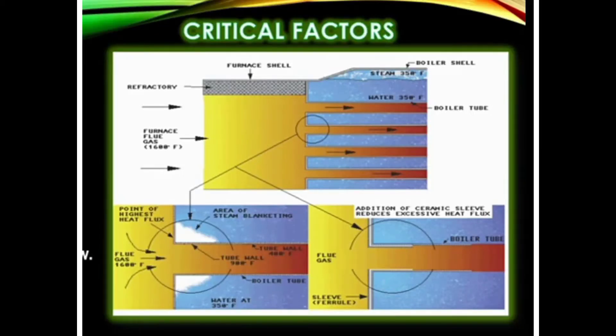Welcome back to learning. Today we are going to discuss steam blanketing, which is one of the causes of boiler tube failure. You can see in this slide that flue gases are coming from the left side at 1600 Fahrenheit and entering into the boiler tubes. This is a water tube boiler, where water is inside the tubes and flue gases are outside.